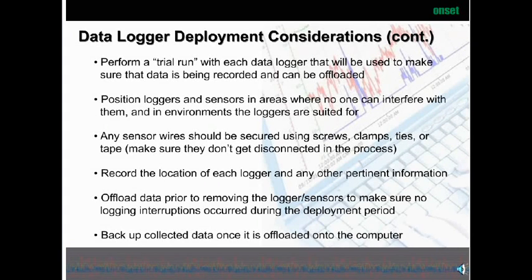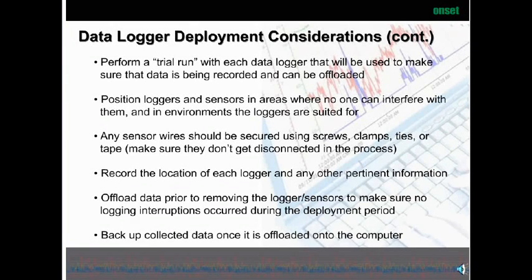Position your loggers and sensors in an area where no one can interfere with them and in the environments the loggers are suited for. People, especially when they see these loggers, like to check them out and see what's going on — you want to get them out of the way so they don't touch them. Any sensor wires should be secured using screws, clamps, ties, or tape. Hide them as best you can. Make sure you don't have doors shutting on wires that can short them out, because sometimes loggers have to be outside a piece of equipment with wires running through a door — when that door closes, it could cut the wires.